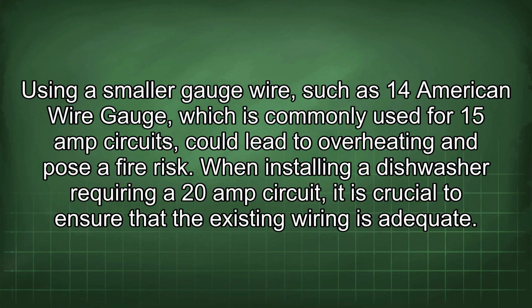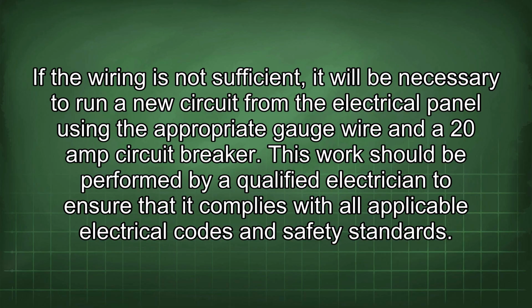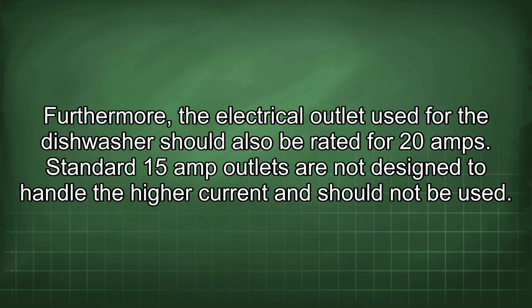When installing a dishwasher requiring a 20-amp circuit, it is crucial to ensure that the existing wiring is adequate. If the wiring is not sufficient, it will be necessary to run a new circuit from the electrical panel using the appropriate gauge wire and a 20-amp circuit breaker. This work should be performed by a qualified electrician to ensure that it complies with all applicable electrical codes and safety standards. Furthermore, the electrical outlet used for the dishwasher should also be rated for 20 amps.